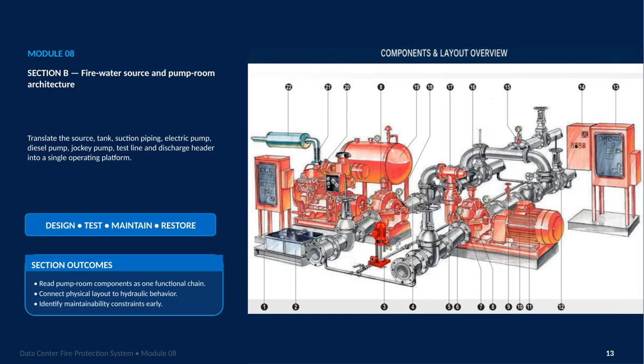Module 08, Section B, focuses on fire water sources and pump room architecture. The central idea is to stop viewing each component as an isolated piece of equipment. Instead, I want us to understand the source, storage tank, suction piping, electric pump, diesel pump, jockey pump, test line, and discharge header as one operating platform. The goal is an integrated, maintainable fire protection system.